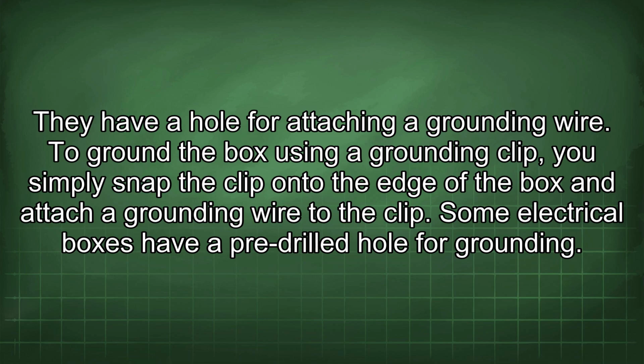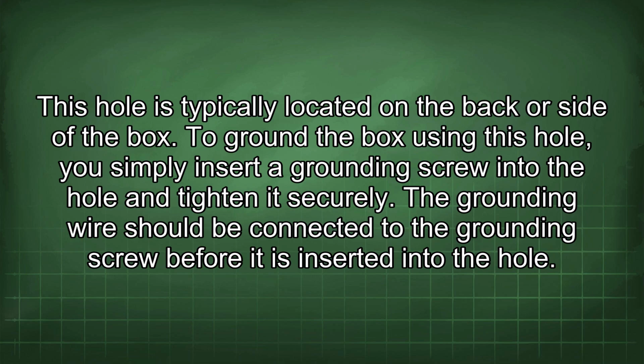Some electrical boxes have a pre-drilled hole for grounding. This hole is typically located on the back or side of the box. To ground the box using this hole, you simply insert a grounding screw into the hole and tighten it securely. The grounding wire should be connected to the grounding screw before it is inserted into the hole.